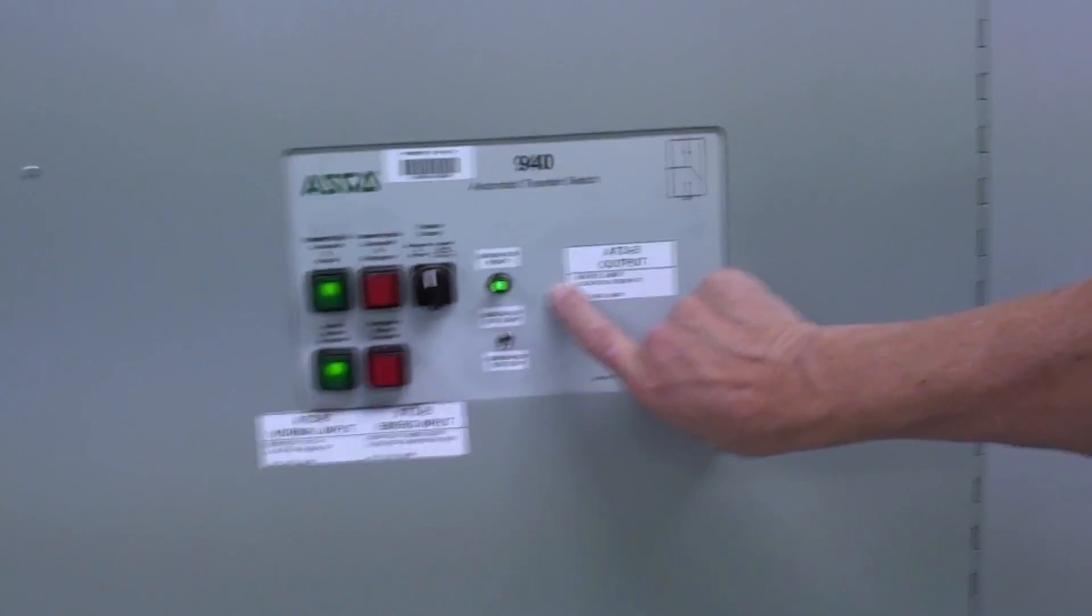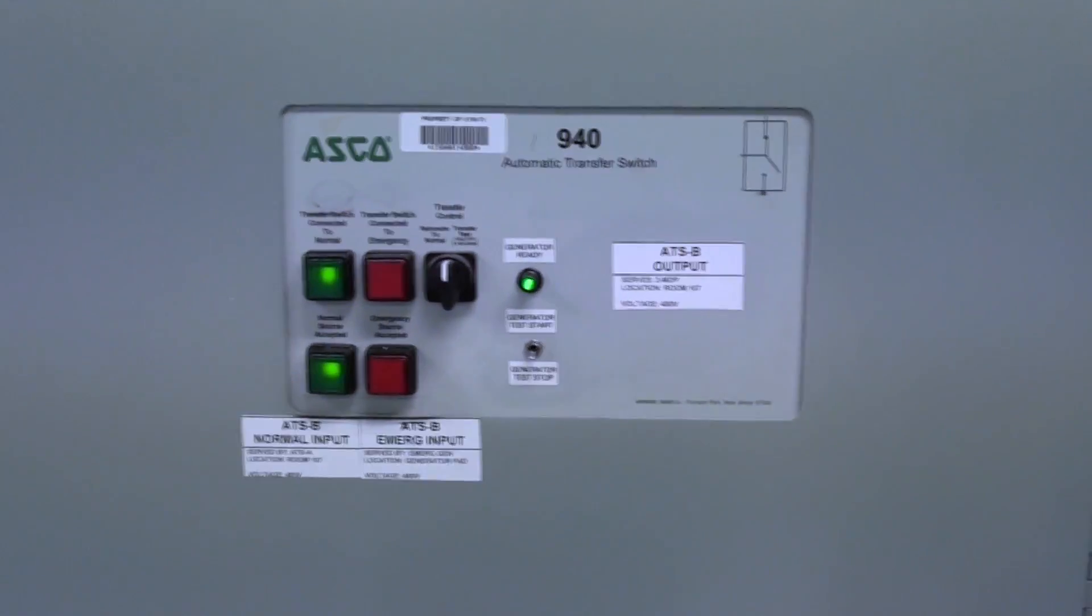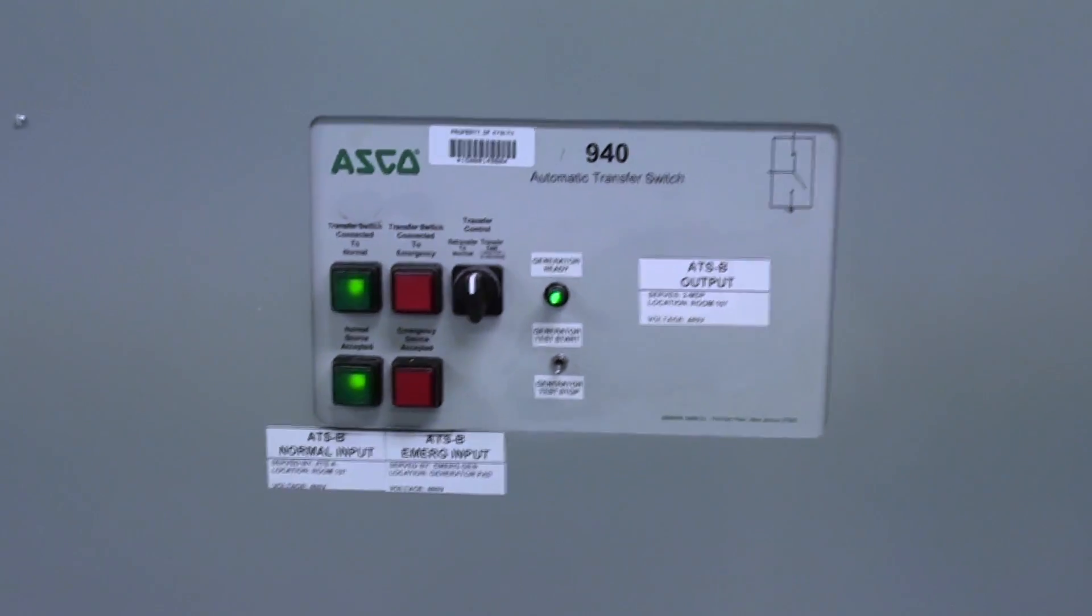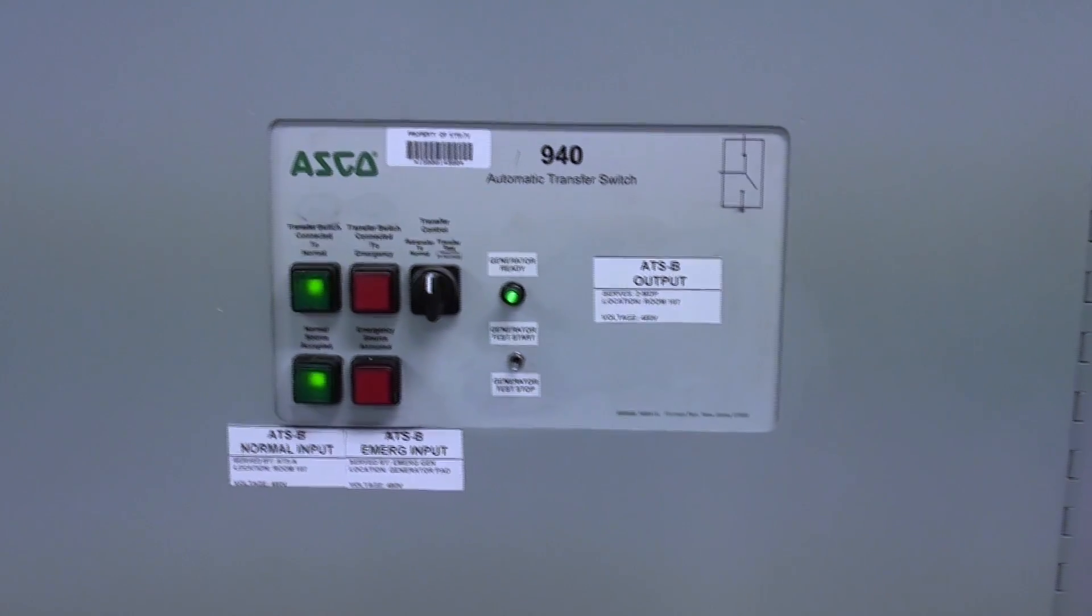Basically I have a switch that starts the generator, waits for the generator to make power and frequency, and switches to it. We have enough fuel here to run about 80 hours, which is about three and a third days.